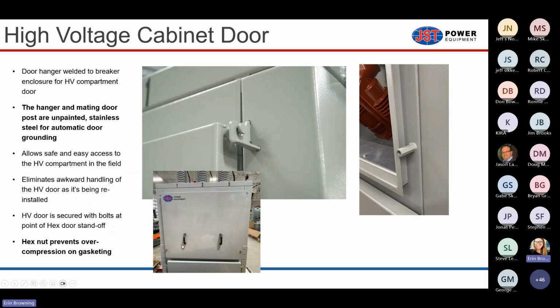The high voltage cabinet door, this is the aluminum version with the handles on it. So this is super light. If you guys saw this at IEEE and were able to pick it up, you know that it's extremely light, easy to handle. It's easy to install because we have these little hangers that are welded to the front of the cabinet, and the high voltage door has these rods that fall right into the hanger. The production units are unpainted, so they actually serve as a grounding point for the breaker when it's installed.